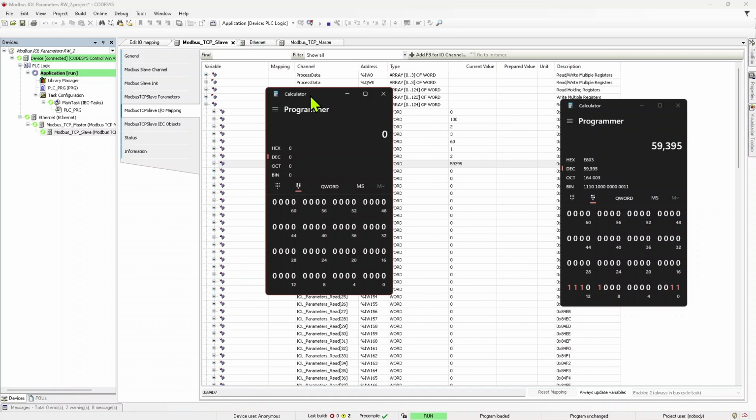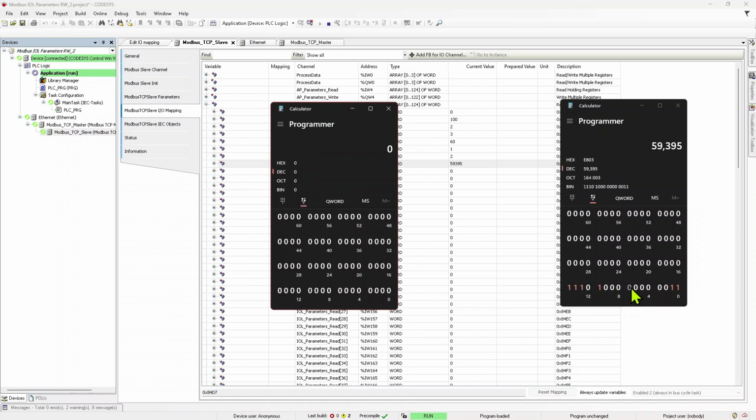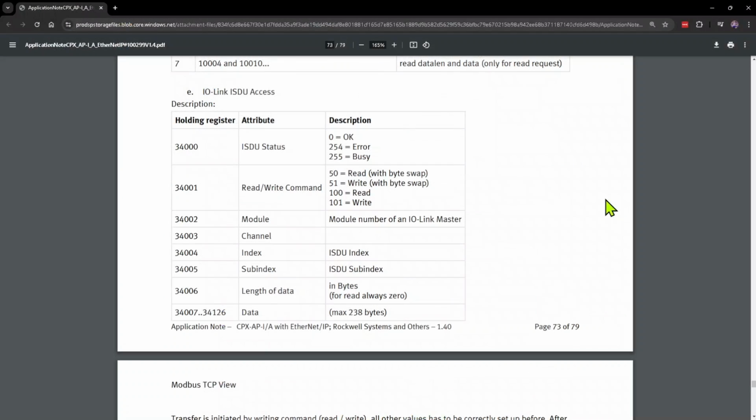So here you can see we have 2 bytes, from 0 to 7, right? And then from 8 to 15. These are just basically swapped. If I swap them here on the left calculator, we should get a value of 1000. So these bits, I'm going to send them to position 8 and 9. And then these bits, I'm going to send them starting from position 0, which would be this, and this, and this. And there's your value, 1000. So in other words, using the 50 helps you deal with data that might be swapped depending on the device.